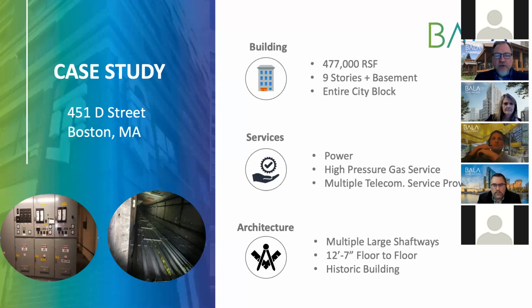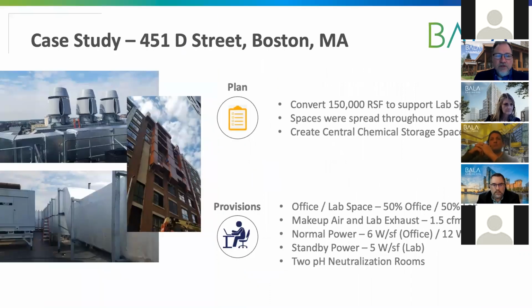So if you look at the images here, you'll see that the electrical gear is there on the left. The other picture on the bottom is the actual elevator shaft that got converted to a vertical utility shaft. Next slide. So here on the roof, you'll see these 3 Strobic fans. I call them my stormtroopers. They're combined into a combined plenum. One is redundant. These things are designed to suck air in from the ambient and increase the total volume to increase my discharge velocity. We want a minimum 3,000 feet per minute out of that cone, and that can be noisy. So you can put attenuation on the cone if you need to, but back to the requirement for an acoustical consultant. But that's the Strobic fan array.